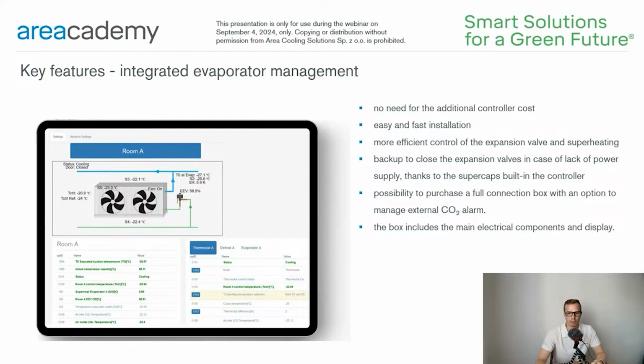And in case of lack of power supply, there are supercaps built in the controller with enough backup energy to close the expansion valves. There is also the possibility to purchase a full connection box with an option to manage an external CO2 alarm. And the box includes the main electrical components and display.